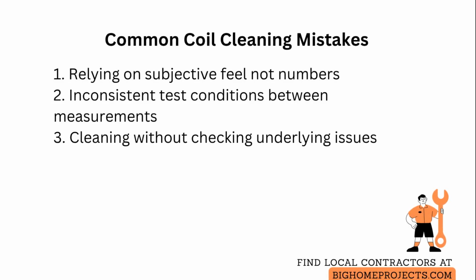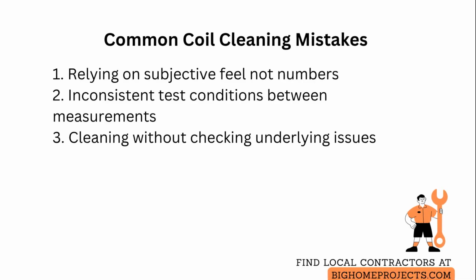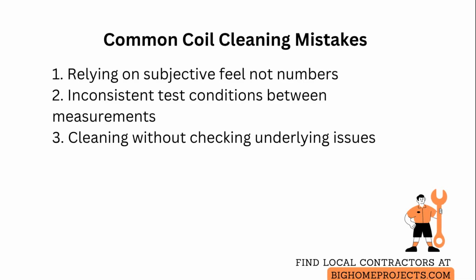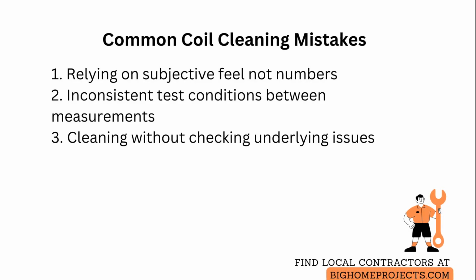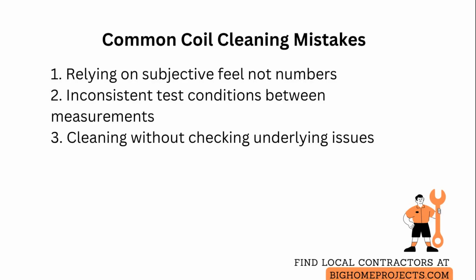A third frequent error is cleaning without checking for underlying problems like restricted airflow or refrigerant imbalance that mimic coil dirt. If readings do not improve after cleaning, inspect filters, ductwork, fan operation, and refrigerant charge before declaring the coil fixed.